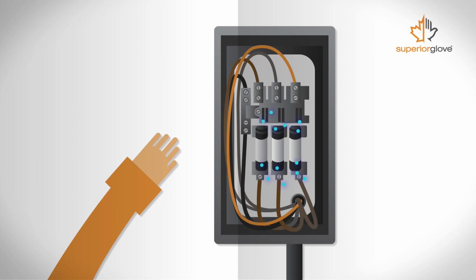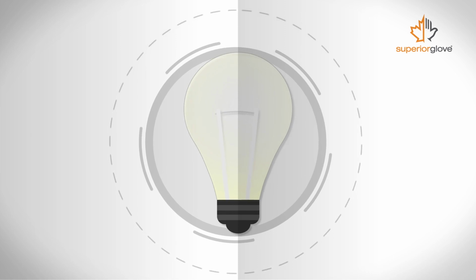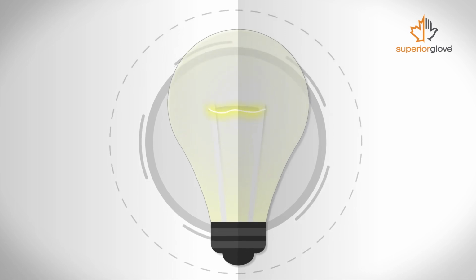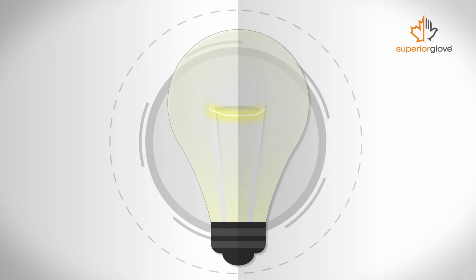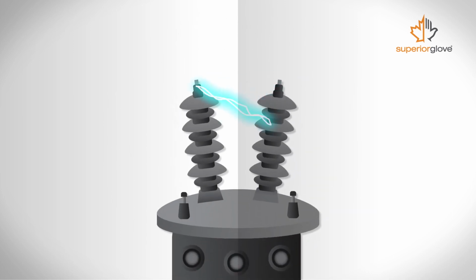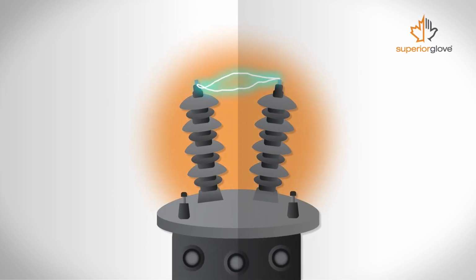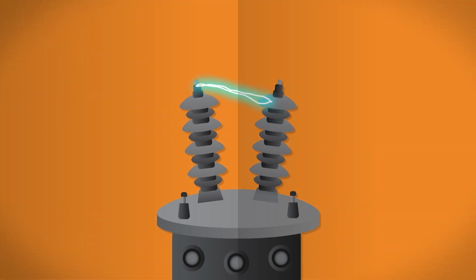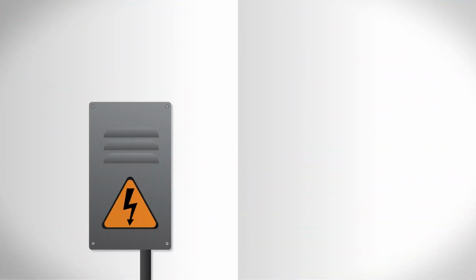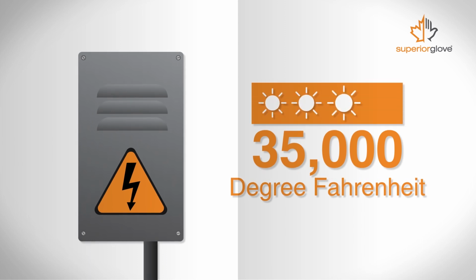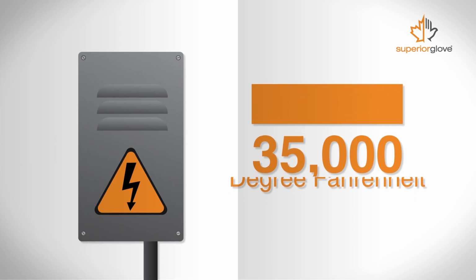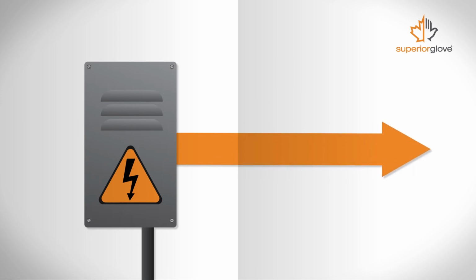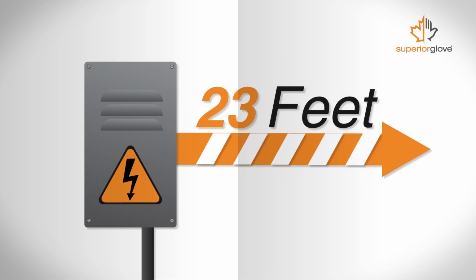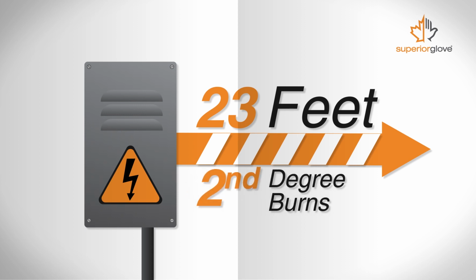As the electrons push off between the conductors, an arc occurs. You see this every day on a micro scale when flicking on a light switch. The little spark inside the bulb is an arc. But on these larger scales, the arc between the two conductors creates heat. A lot of heat. Arc flashes can reach 35,000 degrees Fahrenheit, which is 4 times hotter than the sun. Depending on the voltage of the machine, workers up to 23 feet or 2 car lengths are in danger of second-degree burns. So, how do you protect yourself from one?